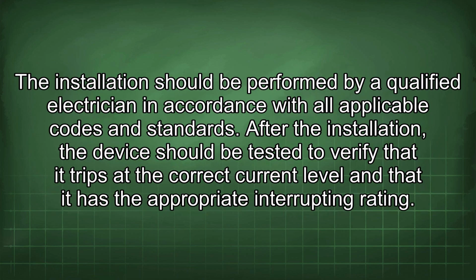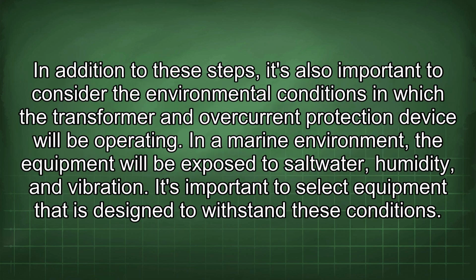The installation should be performed by a qualified electrician in accordance with all applicable codes and standards. After the installation, the device should be tested to verify that it trips at the correct current level and that it has the appropriate interrupting rating. In addition to these steps, it's also important to consider the environmental conditions in which the transformer and overcurrent protection device will be operating. In a marine environment, the equipment will be exposed to saltwater, humidity, and vibration. It's important to select equipment that is designed to withstand these conditions.